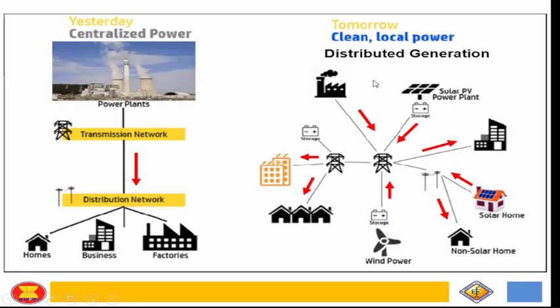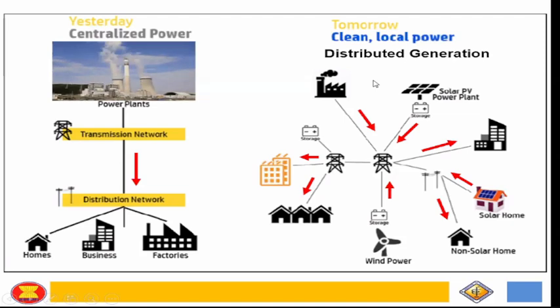Okay, but from a technical perspective, it is one direction, a centralized grid serving the customer through transmission lines, with the grid as the primary source. So this unidirectional power flow simplifies protection requirements, allowing the use of non-directional overcurrent protection without the need for a voltage element as a polarizing quantity of directional overcurrent protection.